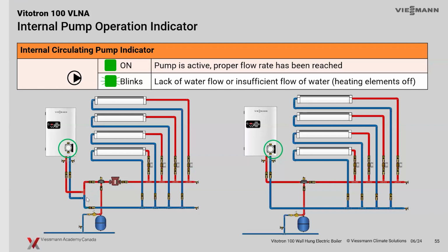So we're showing primary-secondary on the left-hand side, versus where you might see more of that blinking LED when you don't have primary-secondary and you're using one pump that has to push through all these zones and the pressure drops associated with them.